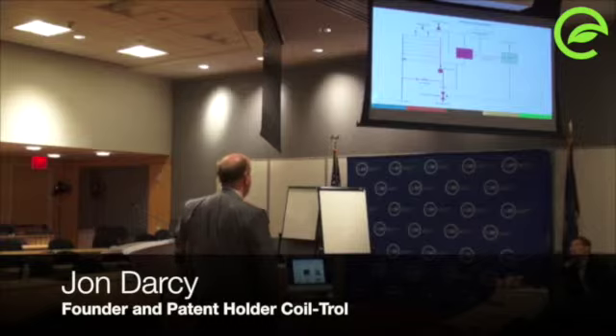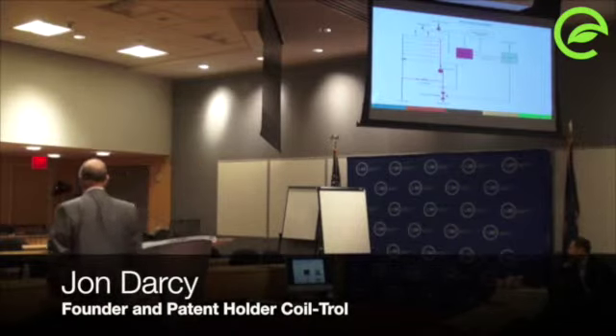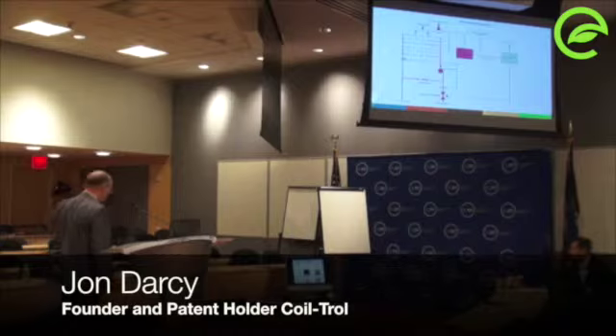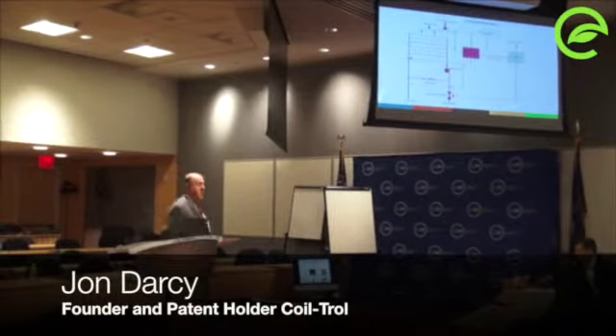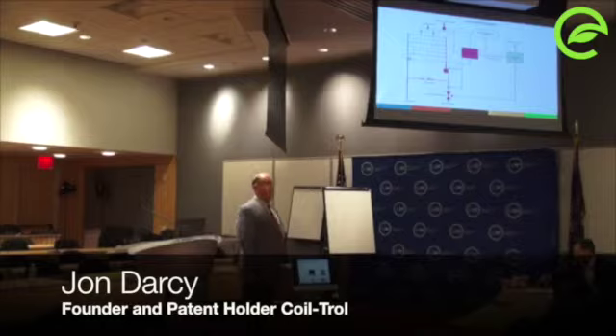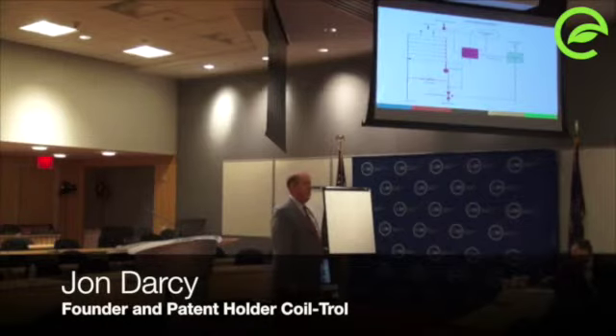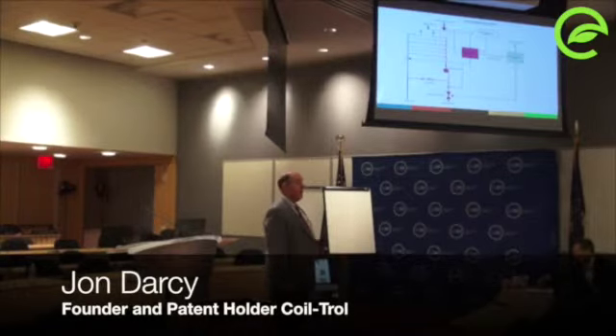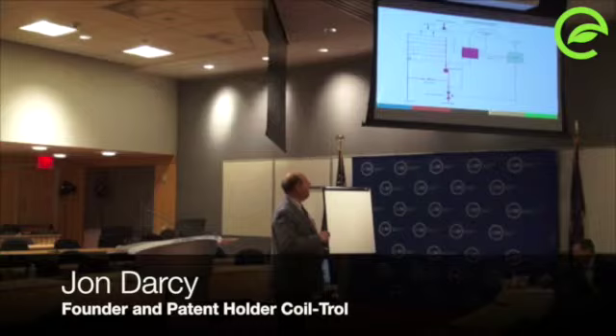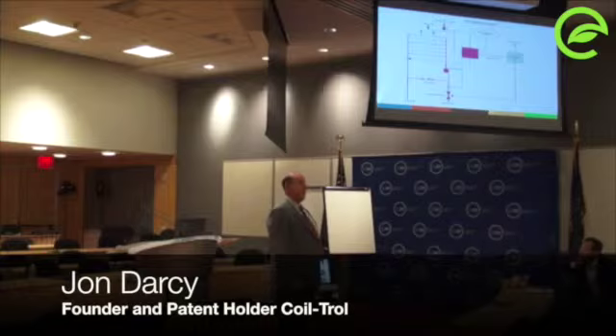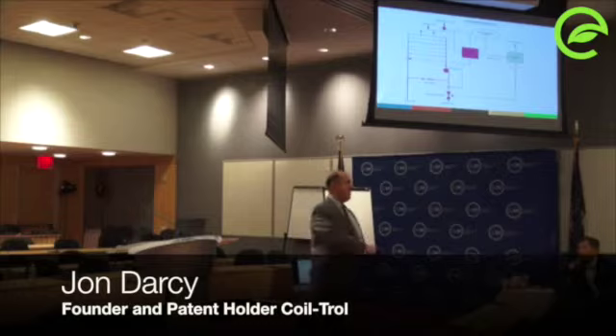What we do is we look at your coils. If you don't have the data on your coils, we just take the physical measurements of the coils, the rows and cross-sectional area, and we run the coils through that coil selection program, so we know where min and max is and the best place to operate that coil. And then chances are there's probably only 3 different size pumps: one for 10,000 CFM, one for 50,000 CFM, and one for 100,000 CFM. Everything fits in between.